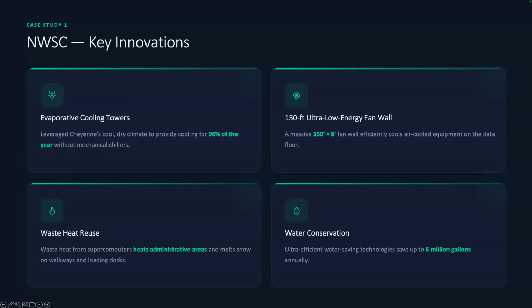One of the other novel things we did at NWSC—because water is a real constraining resource, and in the current environment where we haven't had enough moisture they may put us on restrictions and we'd pay a lot more than originally planned—for that facility we went to zero blowdown technology. We soften the water, add silica, and basically on the internal sections of the pipe it produces a very thin coating of sedimentary rock inside the piping that stops all corrosion.